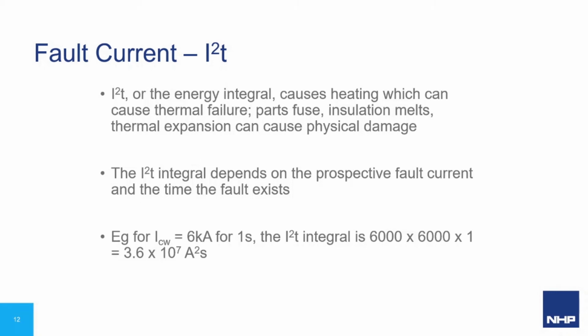From the previous tests that we just witnessed, we arrive at two crucial figures. The first value is the I squared T, or the current squared multiplied by time. This is known as the energy integral. This value tells us the effect of heating, which can cause thermal failure, parts to fuse, insulation melting, and thermal expansion, and can cause significant physical damage.